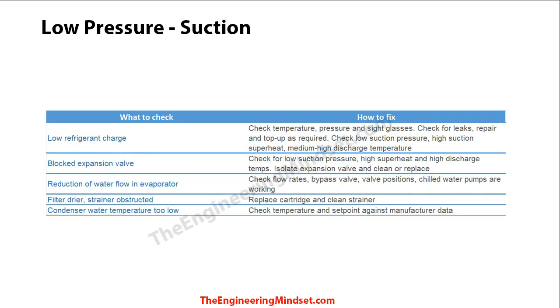For low pressure on the suction side, this could again be due to a low refrigerant charge — check around the system and top up if needed. Don't forget to check for leaks, as refrigerant that's leaked has gone somewhere. One of the more common causes is a blocked expansion valve — clean or replace it if needed.